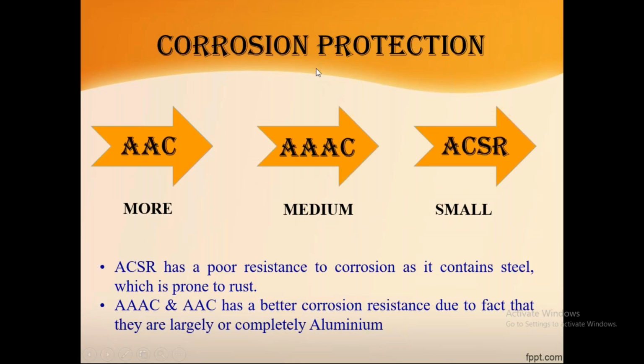Next is corrosion protection. Corrosion protection mainly depends on where the transmission lines are located. In some areas there are chances of more rainfall; there we have to use AAAC conductor. Why? Because this conductor is completely made of pure aluminum, 99.7%, and aluminum has more resistance to corrosion, so there's no chance of corrosion in this conductor.